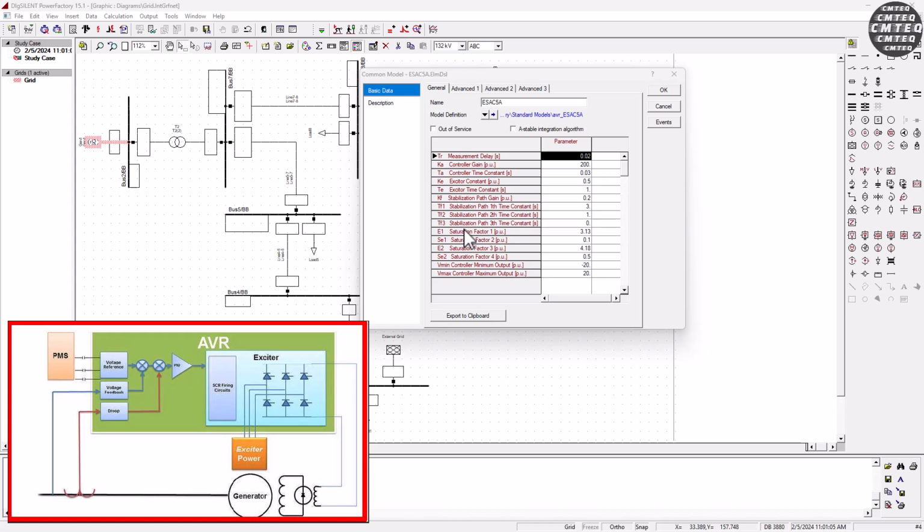So we know that it does measurement. Where does it do the measurement? Let's say this is where our synchronous machine is attached, to this bus bar here, which means the AVR system must do measurement relative to this bus bar. So it must monitor the terminal voltage. Then it must do a comparison: it must compare this voltage to a reference voltage that's set internally, as a set point.